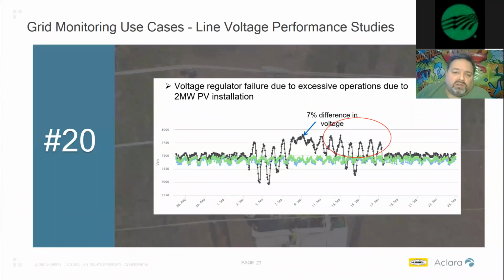Another case we've called out is application number 20, where you can start to see voltage regulators fail due to excessive operations. We can start to tell when your voltage regulators are about to fail. Not only can we give you conductor slap during windy days, not only can we do things like vegetation detection like we talked about earlier, we can also tell when some of your equipment is starting to fail, so you can be proactive and get out there before it's a full-on failure.